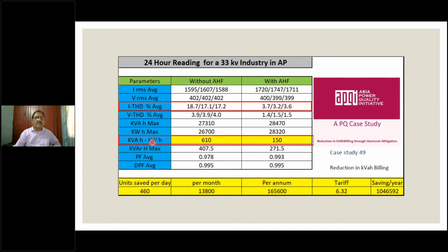The difference between kVAH and kWH was 610 with this kind of harmonic. It was brought down to 150. So the per day saving was 460 units. Per month saving was 13,800 units. And the annual extrapolated saving was 1,65,600 units. So at that time in 2016, the tariff was 6 rupee 32 paisa, and the client saved 10,46,000 rupees per annum because of the provision of harmonic filters.